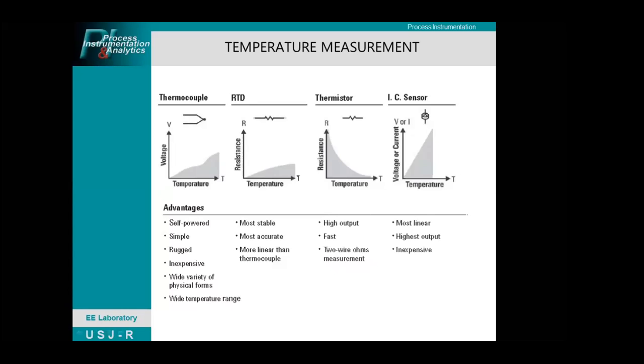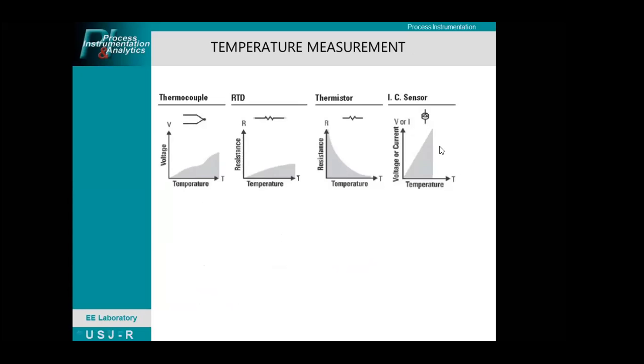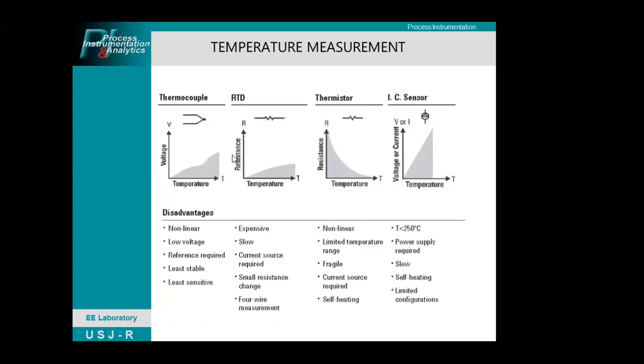And of course, these 4 common temperature measurements also have disadvantages. For thermocouple: nonlinear, low voltage, reference required, least stable, least sensitive. Okay, so you have to balance the advantages and disadvantages of each temperature measurement. For the RTD: expensive, slow, current source required, small resistance change, 4-wire measurement.